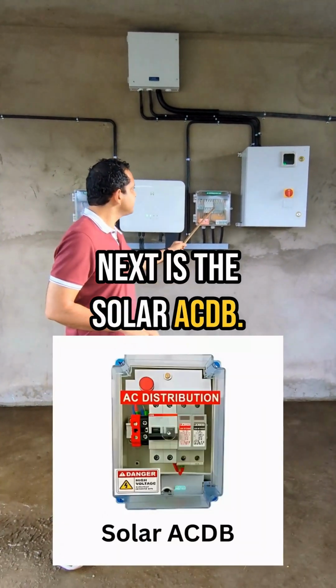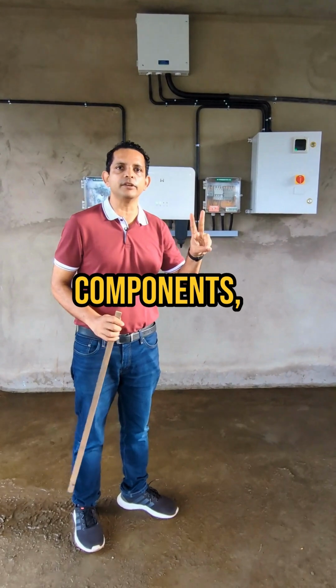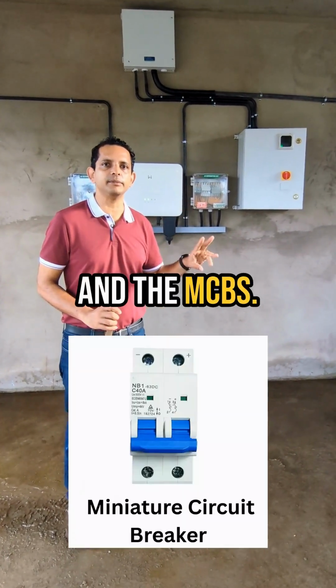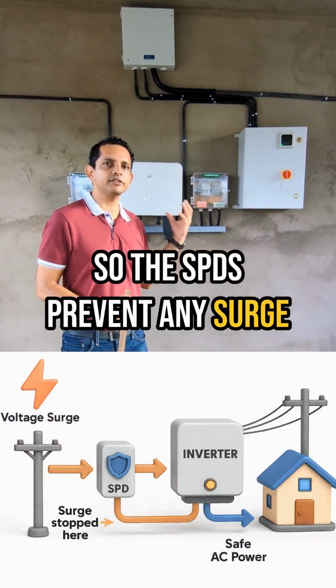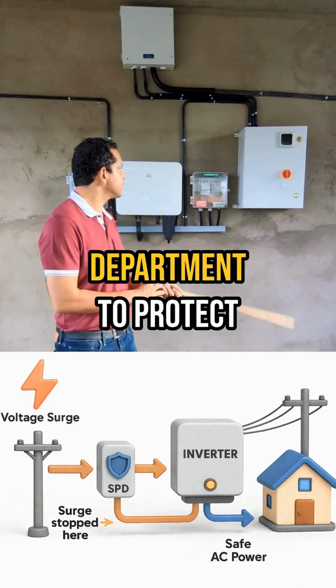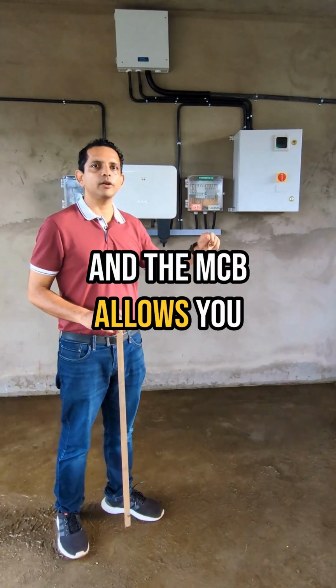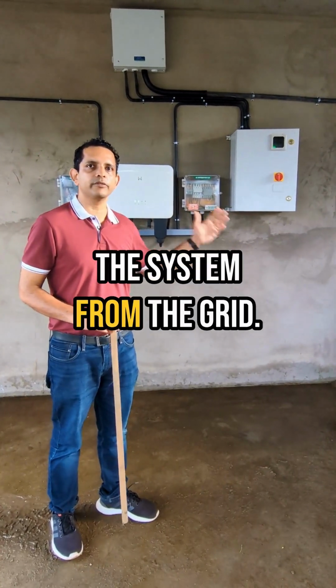Next is the solar ACDB. The ACDB contains two components, the SPDs and the MCB. The SPDs prevent any surge of voltage from the electricity department to protect the inverter, and the MCB allows you to turn off or isolate the system from the grid.